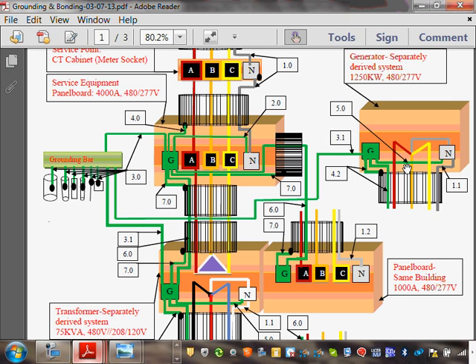Really, just scale this down to lower voltages, nothing will change. The only thing that will change is the sizes, the size of the conductors. That's the only thing that changes. That applies to 480/277, 208/120, as well as 240/120, single phase and 3 phase. So nothing really changes. And a 50 kW generator, you ground and bond exactly like a 1250 kW generator. Smaller generators, portable ones, have their own rules. Any comments, guys, about what you have in front of you? So that's what we basically have.